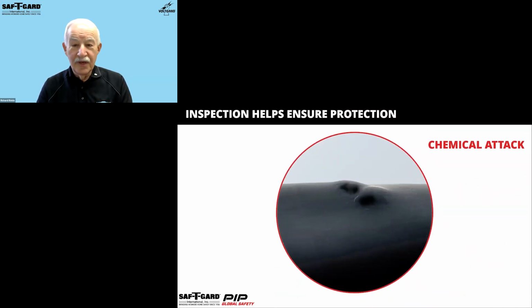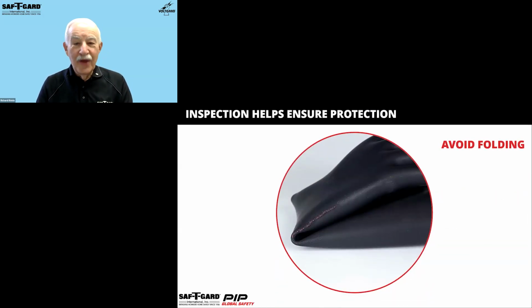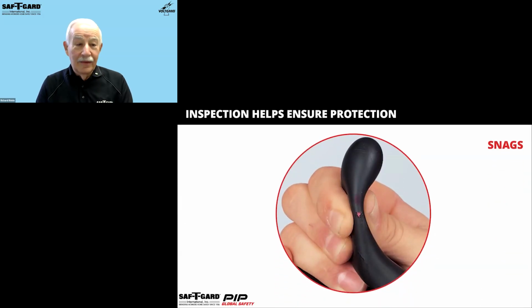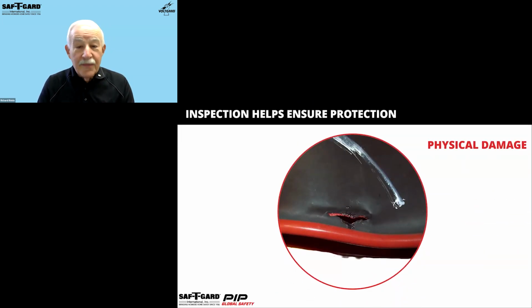Oils and petroleum compounds can cause swelling of the rubber. Come on, folks, don't refuel your truck with your rubber gloves on. It's not good practice. Avoid folding them. The strain on the rubber at a folded point is equal to stretching the rubber at twice its length. So don't strain the rubber. And sometimes if there's a snag that gets through that leather protector glove, it can also cause a snag in the rubber insulating glove. Wood, metal splinters, and other sharp objects can snag or tear the rubber. Also, rope burns, deep cuts, and puncture hazards can be causes for rejection as well. This is the glove that's going to save your life.